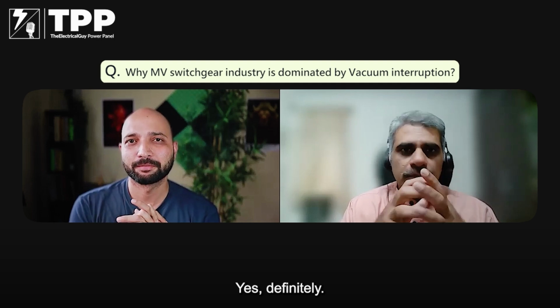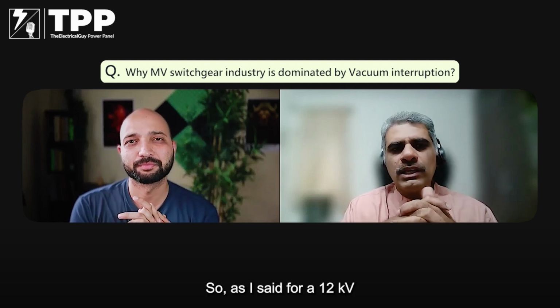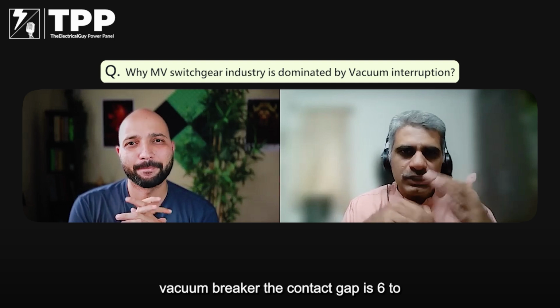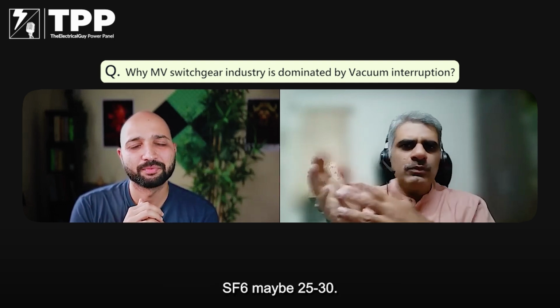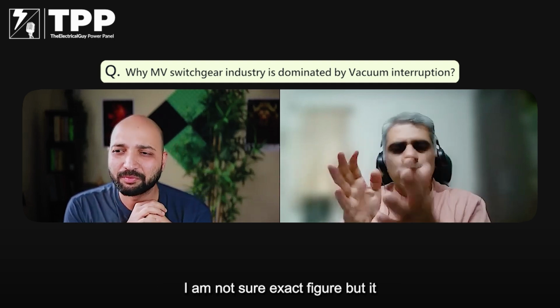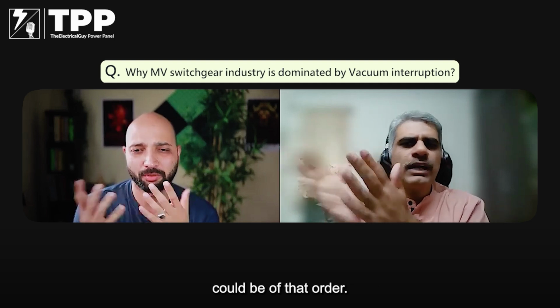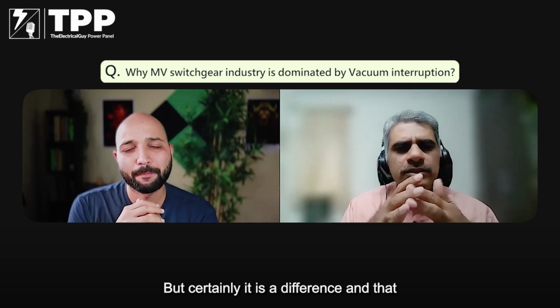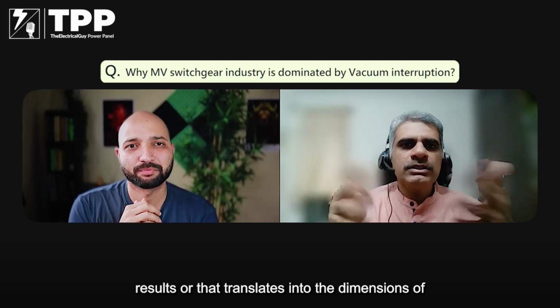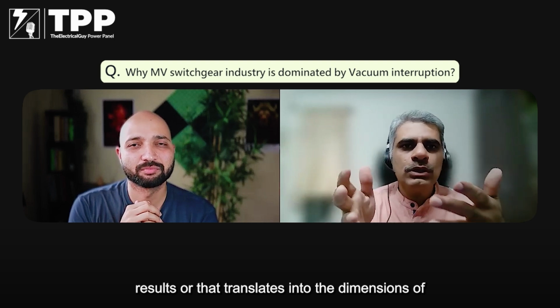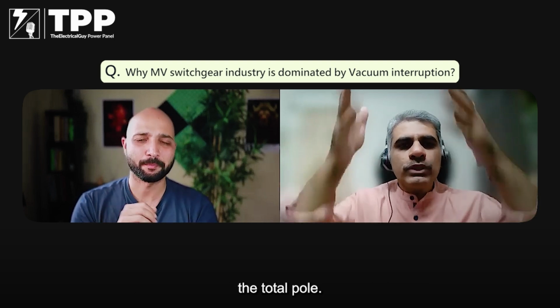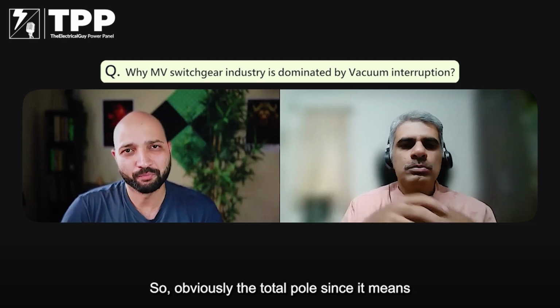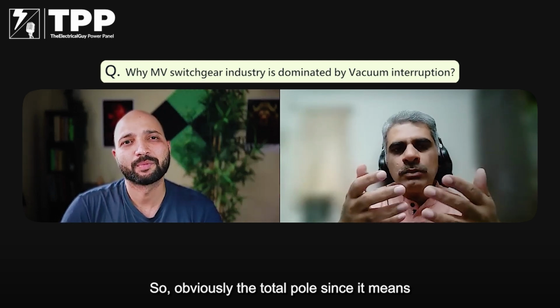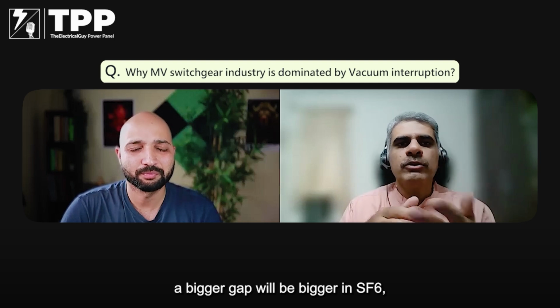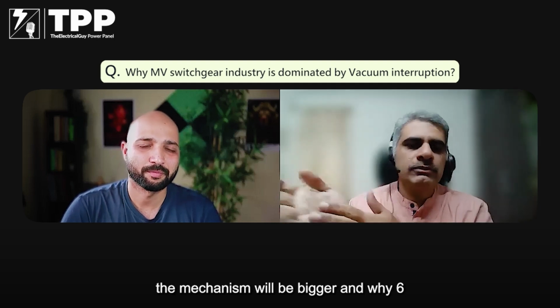So will that also affect the size of the circuit breaker? Yes, definitely. So as I said, for a 12 kV vacuum breaker, the contact gap is 6 to 8 mm, SF6 maybe 25, 30. I am not sure of the exact figure, but it could be of that order. But certainly it's a difference, and that translates into the dimensions of the total pole. Since it needs a bigger gap, the pole will be bigger in SF6. The mechanism will be bigger.